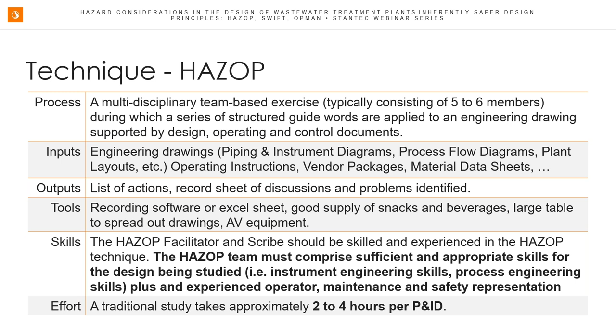So how does it work? Well, the facilitator steps the team through a checklist for each node. For example, the attribute may be flow rate, which I circled, and the guide word may be "no". The team then decides if there could be a no flow in this line situation. If so, what would cause it? They note that there is a manual isolation valve with no indicator to SCADA. For example, if this valve were closed and no one knew about it, there would be no flow to the aeration tank. The consequence in that case would be the flow would go to the other tanks. The team then would assess this risk and decide if they can manage it given the current safeguards in place. If not, they would require a change in the design, i.e. a position indicator to SCADA for that valve.